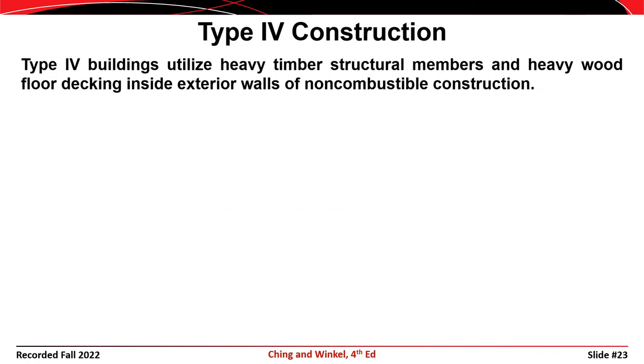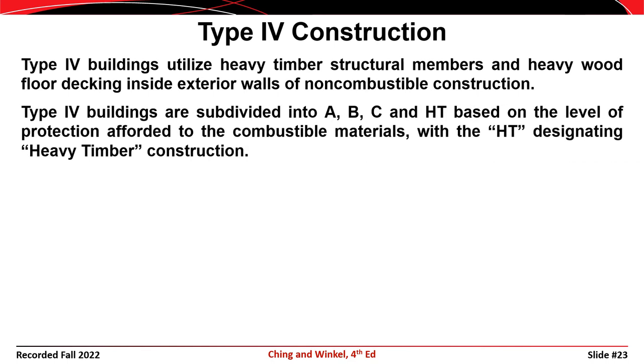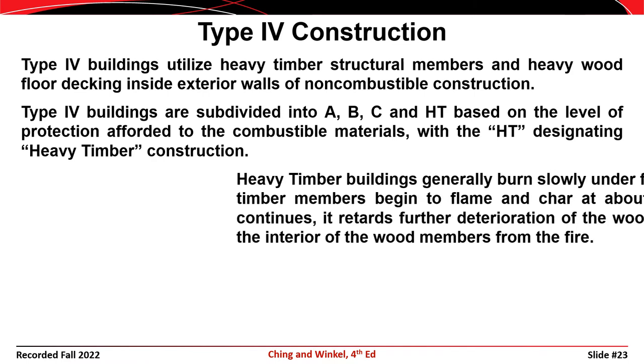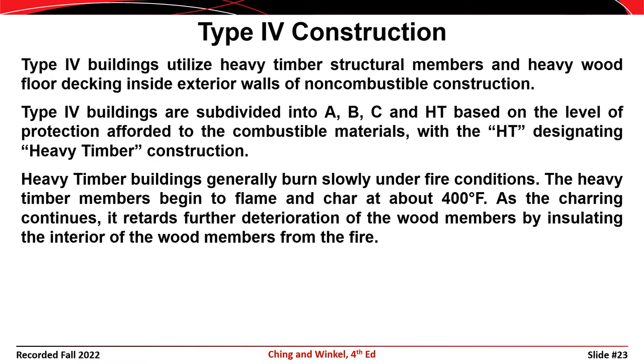Type 4 construction is similar to Type 3 construction with the exception that the entire interior of the structure is constructed of lumber or timber. Type 4A buildings have structural elements that are completely protected with non-combustible protection. Type 4B buildings have structural elements mostly protected with non-combustible protection. Type 4C buildings have most structural elements left unprotected. The HT designation refers to heavy timber construction, where timbers or glue-laminated members tend to develop a layer of char under fire that insulates the core of the members and increases their resistance to fire.